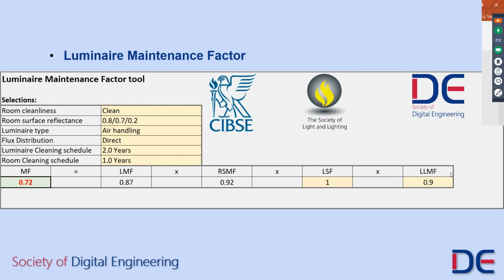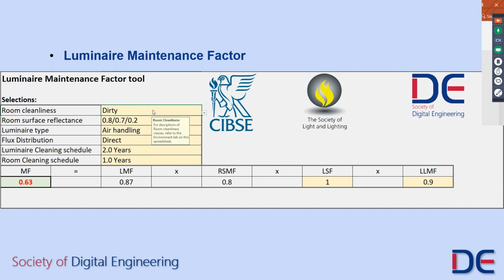So you can ask them what these are and plug them in to your table. Here we can see the overall maintenance factor has been calculated as 0.72. But this is based on a clean space. What if the space isn't a clean space? We want to change it to a more dirty space.